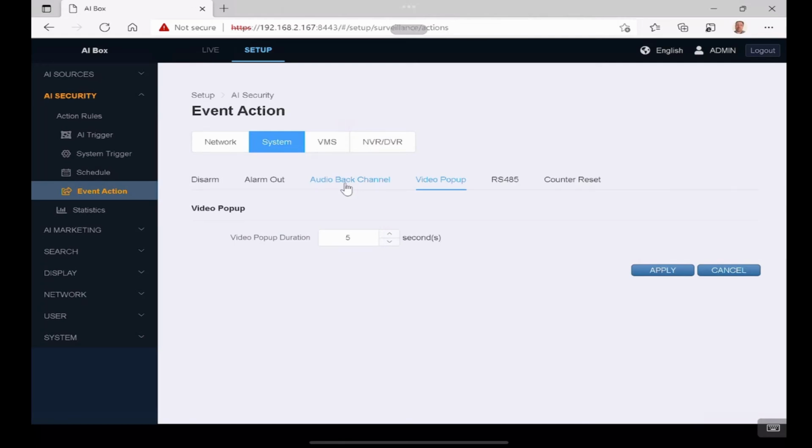With all the different technologies that are out there, I'll use ONVIF as the perfect example. ONVIF has 3 different ways, 3 different flags, just from motion event. And if your manufacturer of a device has not actually programmed for all 3 potential flags, you've only programmed for 1, and your other device, which is supposed to be handshaking with that flag, is using a different one of the 3 options, obviously no handshaking is going to take place. And there's just no way of knowing until you take the devices, put them together, and test if they properly handshake. Proactive is always better than reactive.